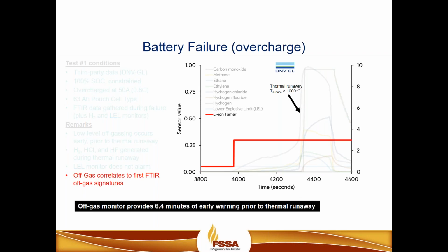And then, of course, as we continue to look at the overcharging event and the off-gas that was associated with it, had we used an off-gas monitor like DNV used in their particular test, that golden time, that early warning detection, could have provided roughly about 6.5 minutes of early warning detection. So during that time period, from when off-gas occurs all the way to thermal runaway, is where we need to work in conjunction with the battery management system to shut down the overcharging of the batteries and eliminate the abuse factor. This will, in a sense, eliminate or prevent the thermal runaway from occurring.